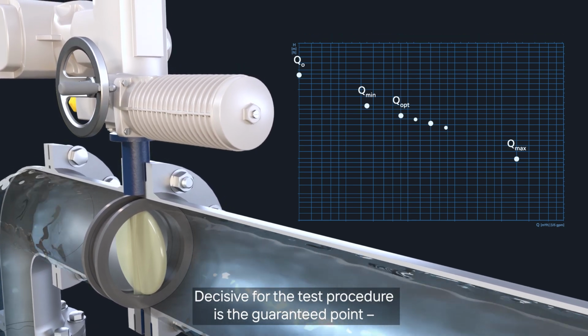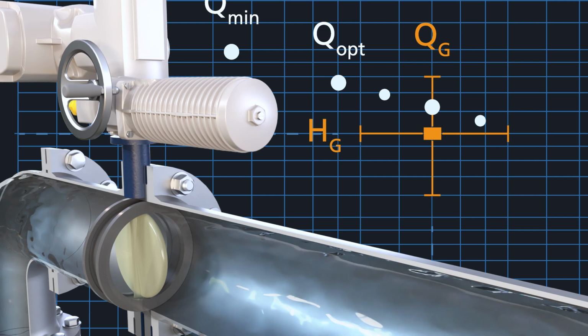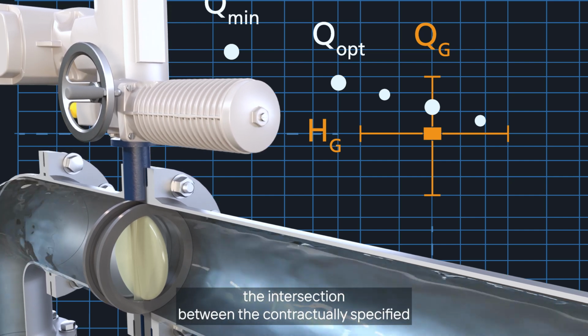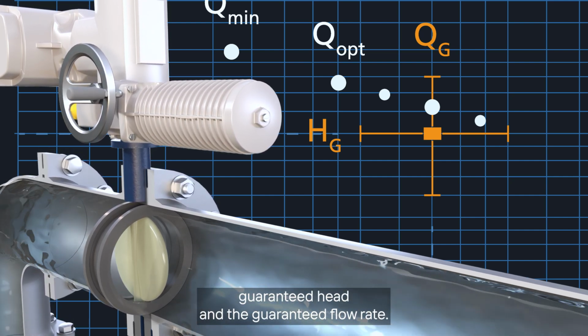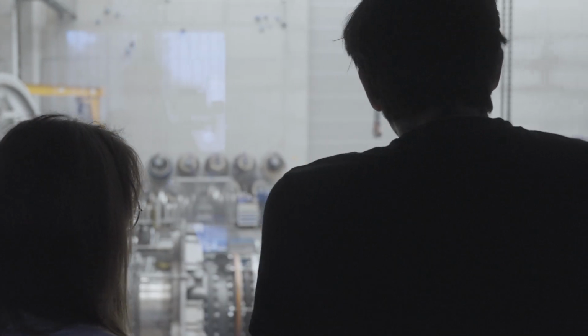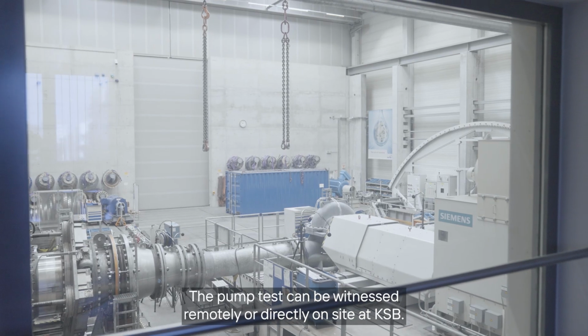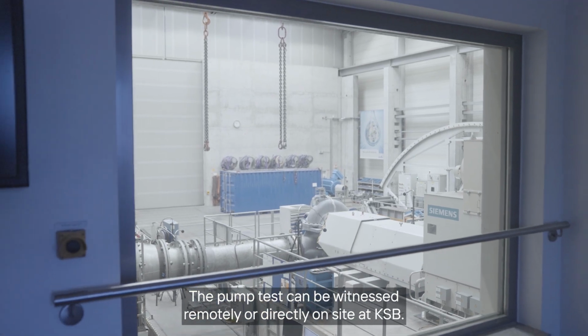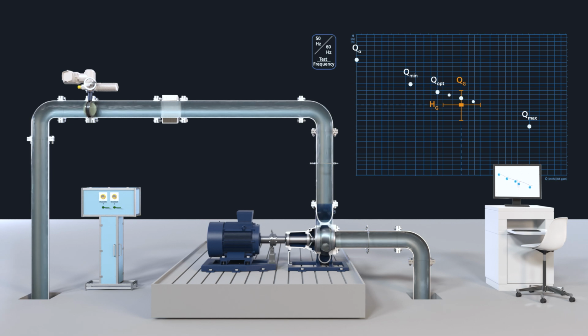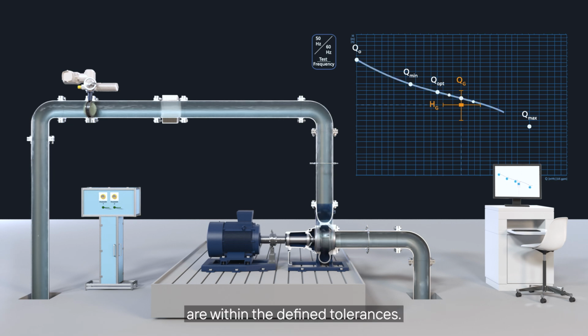Decisive for the test procedure is the guaranteed point, the intersection between the contractually specified guaranteed head and the guaranteed flow rate. The pump test can be witnessed remotely or directly on site at KSB. The pump has passed the test when the flow rate and/or head are within the defined tolerances.